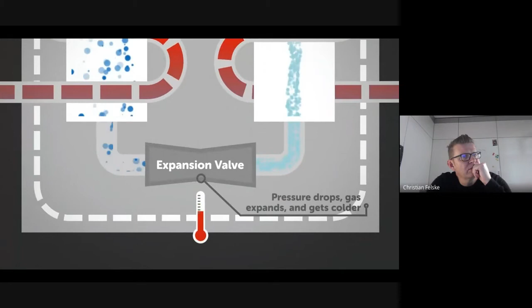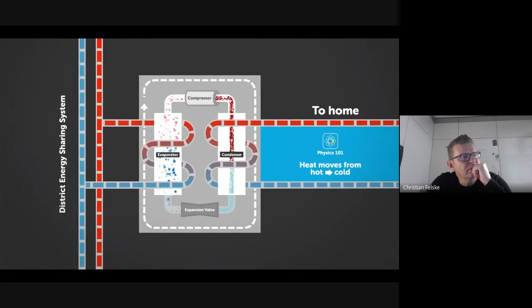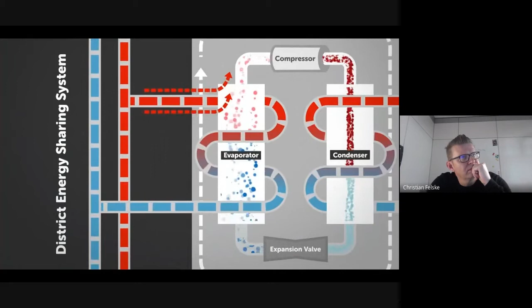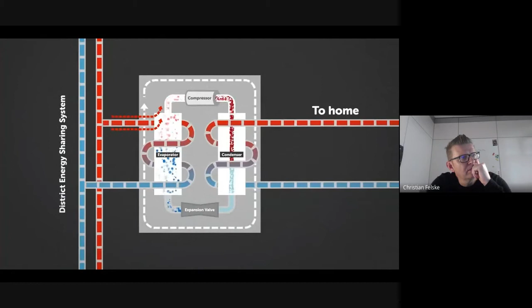But why are we cooling the refrigerant when we're trying to heat? The answer goes back to the basic principle of physics: heat moves from hot to cold. By cooling the refrigerant, it can now take more energy from the warmer water that is in the district energy sharing system's pipes. Once the refrigerant has been rewarmed, the loop starts again.